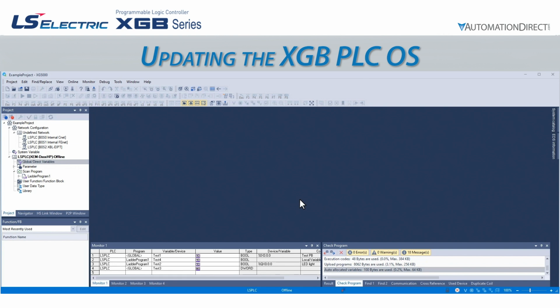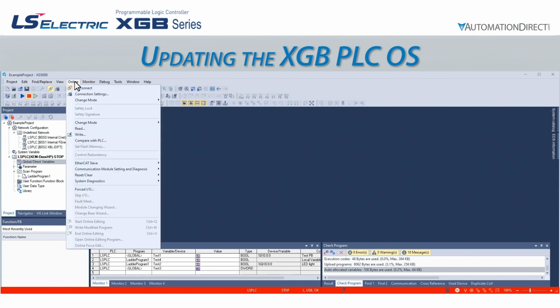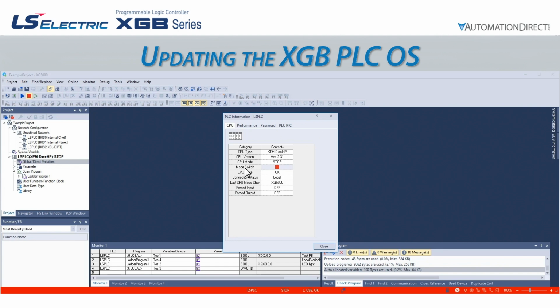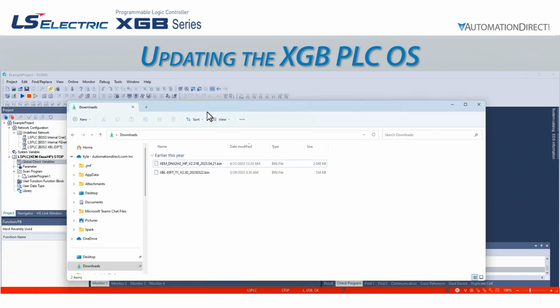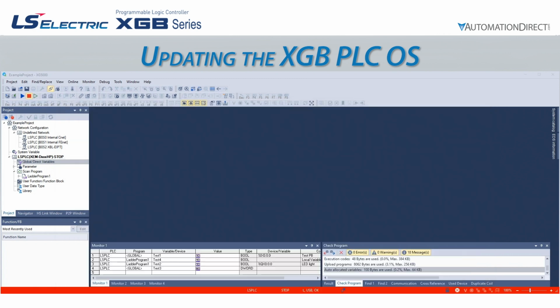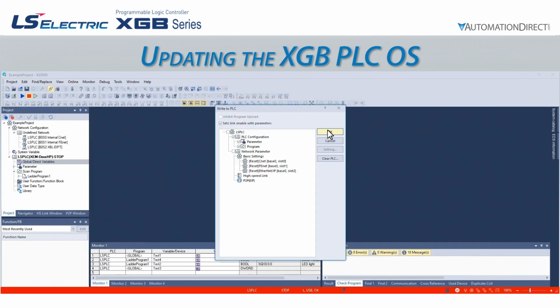Let's verify the CPU is running the OS we want it to. Once XG5000 is back online with the CPU, we can go to Online, System Diagnostics, PLC Information, and under the CPU tab we can look at the CPU version number. We see it matches our OS file revision number of 2.31. We can now rewrite our program to the CPU.